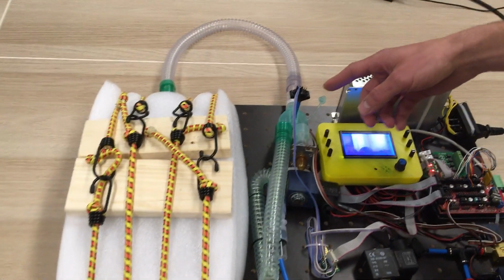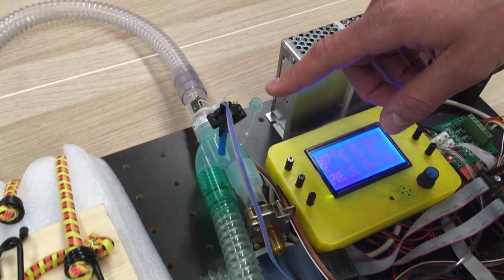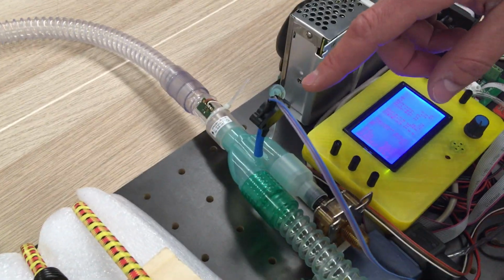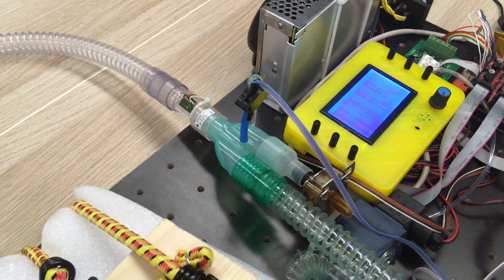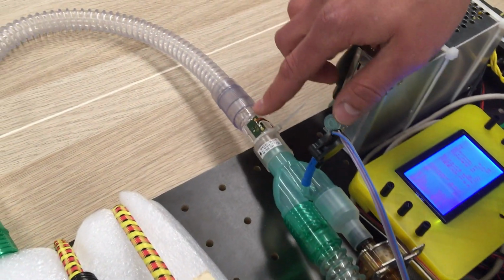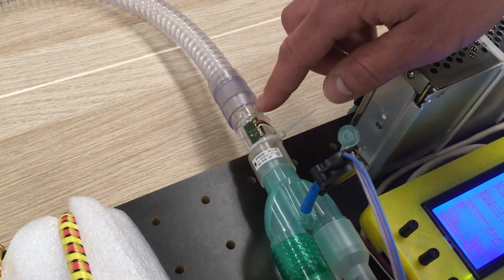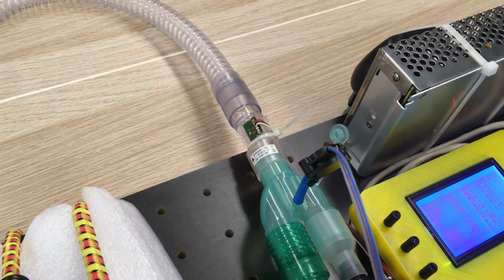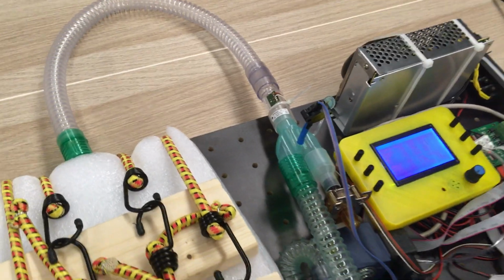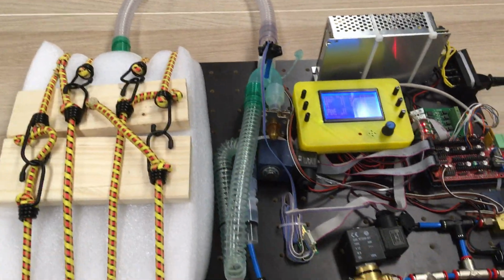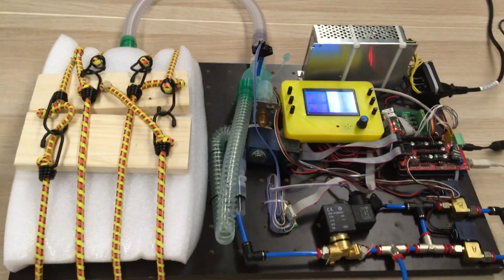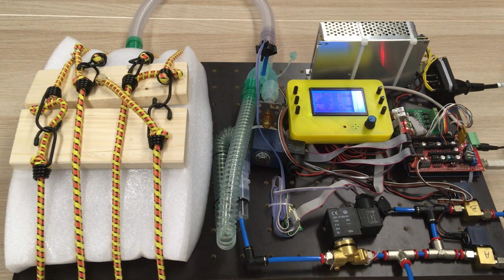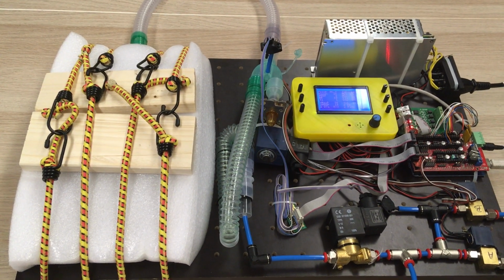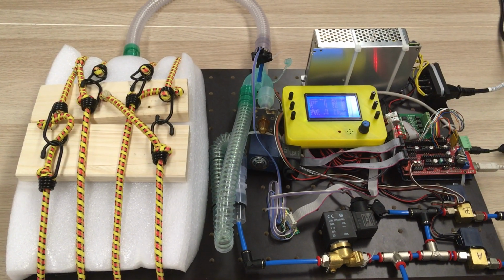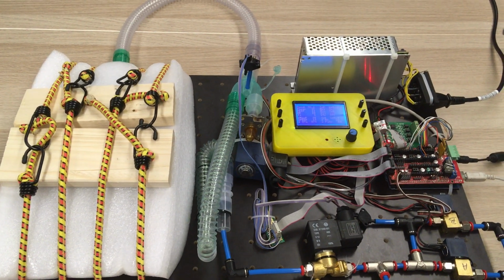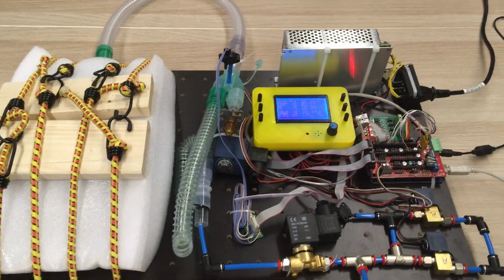There are two sensors here. There is a pressure sensor which is used to monitor maximum pressure and peak pressure, and there is a flow sensor here. This is actually a medical flow sensor which works on the principle of a heated element. So this flow sensor is used to calculate inspired and expired volume. We have a control board here.